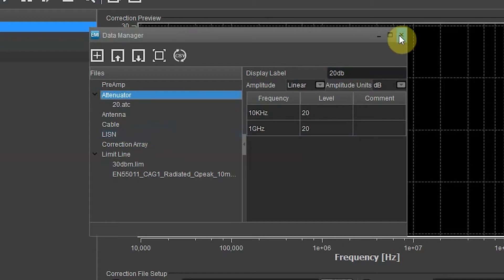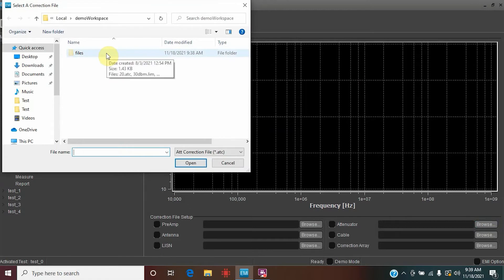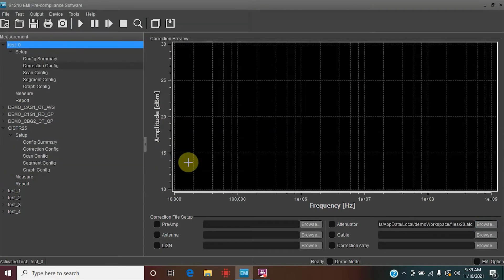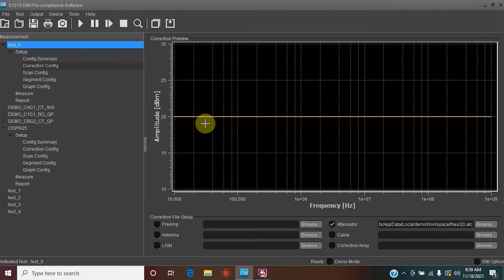Now let's hit the X and go down to our correction file setup. Select Browse — under the demo workspace you'll see the files and find '20.atc'. Hit Open and you will see the map being populated. That's how you know it imported correctly. Let's select Attenuator, and you will see the yellow line indicating the 20 dB correction file has been imported — a great visual way to confirm the file is loaded.